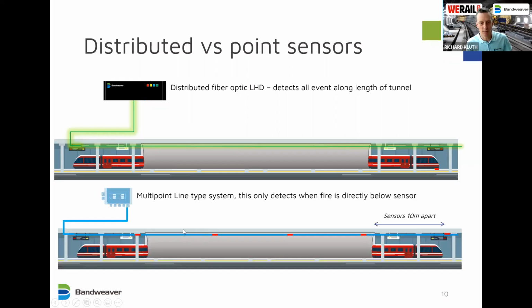If we look at a multi-point line type system, and this is a system with multiple sensors, I believe sort of up to 250, but when you put this in a tunnel environment, they can be more than 10 meters apart at times. And when you have a fire, there's a bit of a lottery as to whether it's below a sensor or not. So in this case, it isn't. In this case, it isn't. And when it isn't, it won't detect the fire till much later, till it really spreads and the heat spreads. In some cases, you will get it, but there's no guarantee that you'll get it every time. So the distributed system has a number of benefits from that perspective.